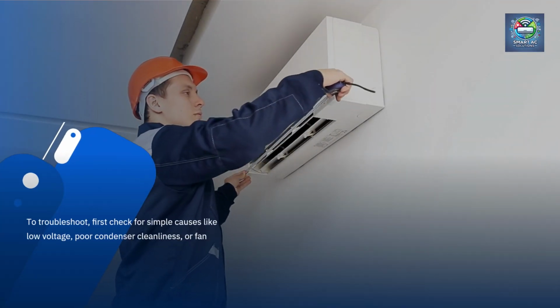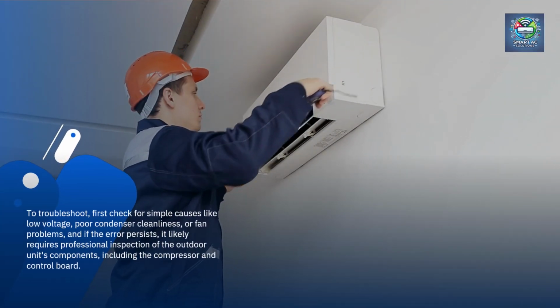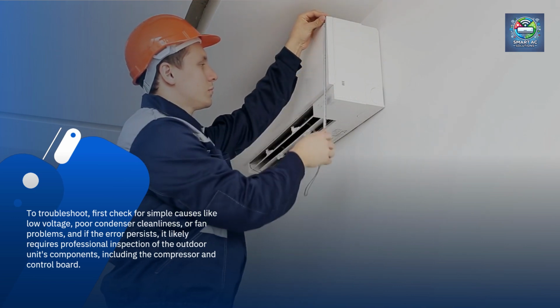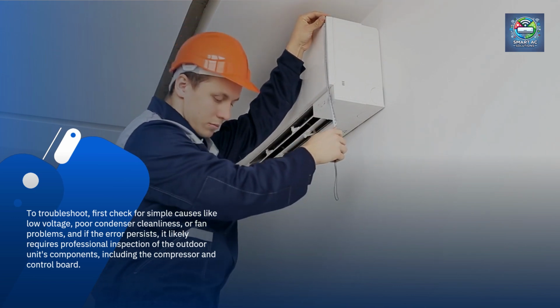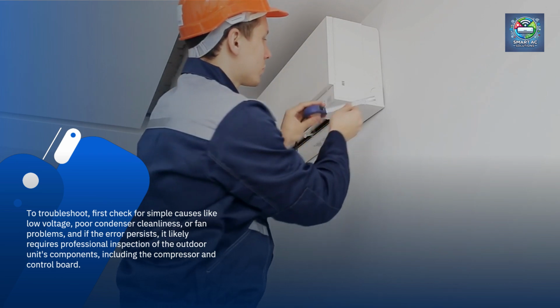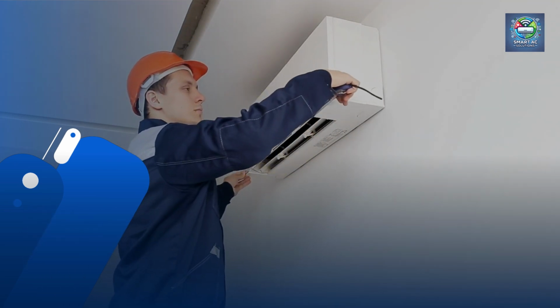To troubleshoot, first check for simple causes like low voltage, poor condenser cleanliness, or fan problems, and if the error persists, it likely requires professional inspection of the outdoor unit's components, including the compressor and control board.